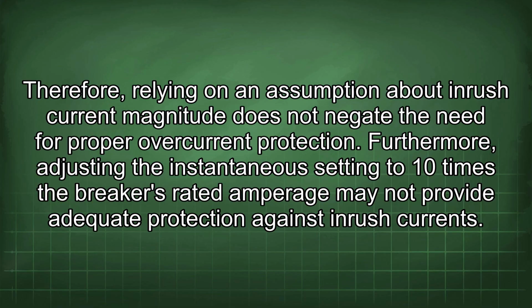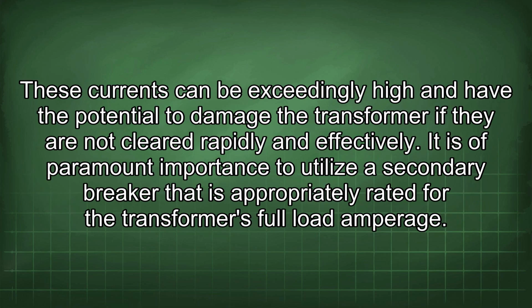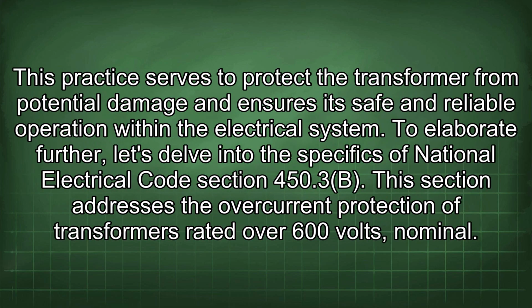Furthermore, adjusting the instantaneous setting to 10 times the breaker's rated amperage may not provide adequate protection against inrush currents. These currents can be exceedingly high and have the potential to damage the transformer if they are not cleared rapidly and effectively. It is of paramount importance to utilize a secondary breaker that is appropriately rated for the transformer's full load amperage.